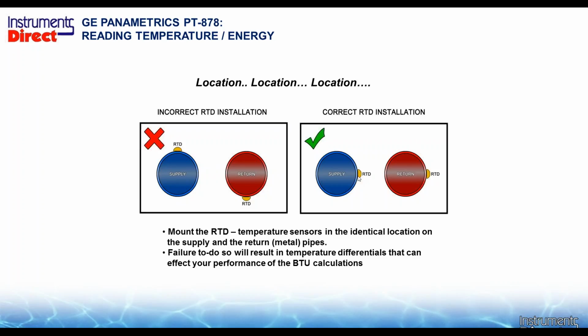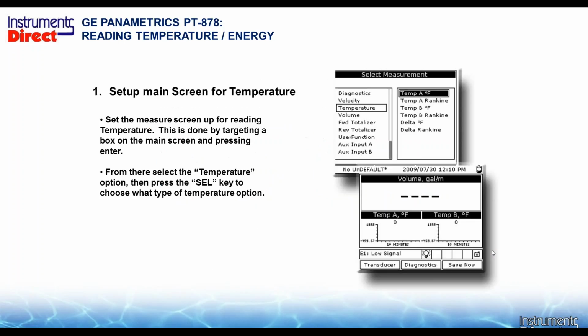What I need to do is have an apple and an apple, same to same. So if I'm putting them on the pipe, put them in the same position. Put this one at 3 o'clock and put this one at 3 o'clock, so the temperature differential between these two is insignificant. A couple degrees of temperature differential can make a significant effect on your BTU calculation. It's all about the temperature. You already have the flow covered, so install it properly and you get good data.